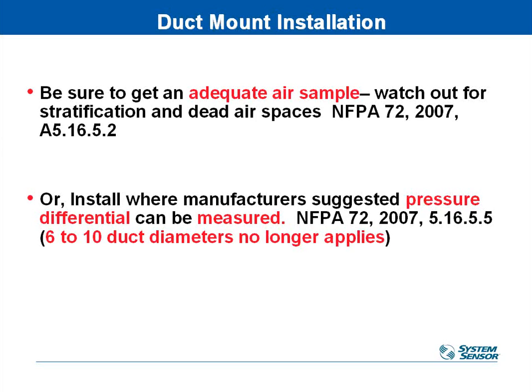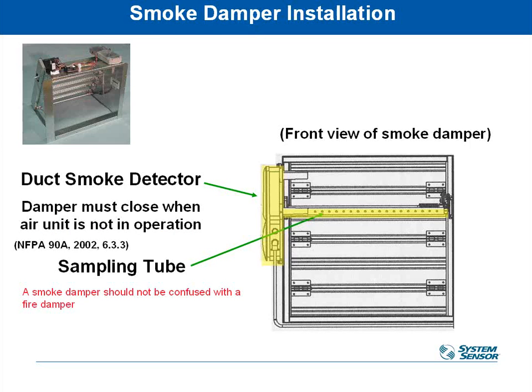You can get a magnehelic gauge, and if you can measure pressure differential between 2 spots where the detector would go, both the intake and exhaust sampling tubes of the detector, then you can go ahead and put it there. But it's safest just to put it where you can get 6 duct diameters, if you can get that. If you're doing a smoke damper instead of equipment shutdown, obviously the detector needs to be on the upstream side of the damper itself to make sure we can sense that before the damper closes.